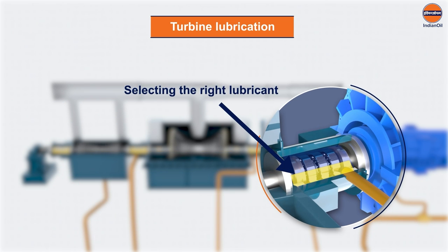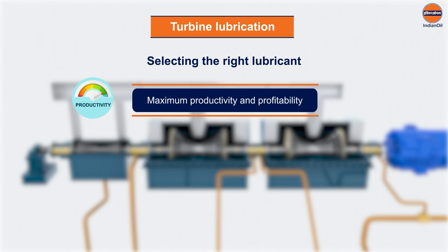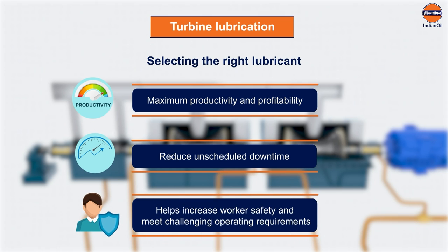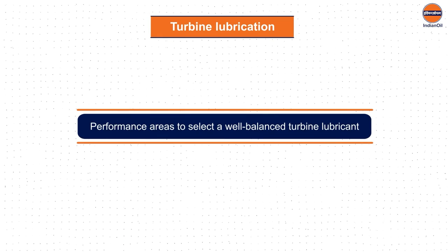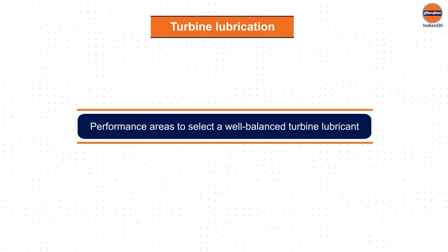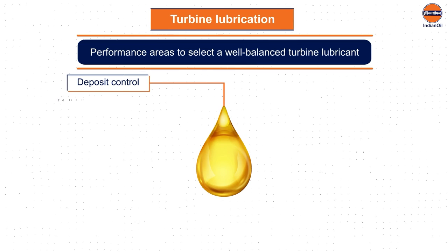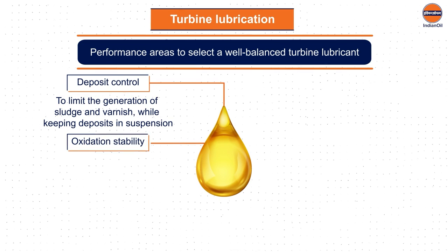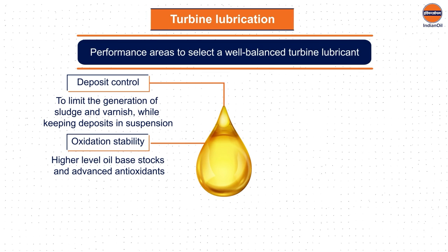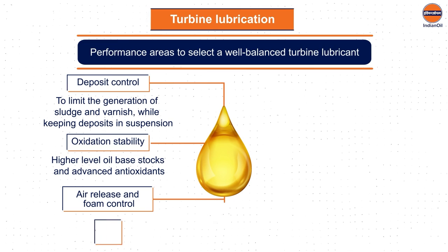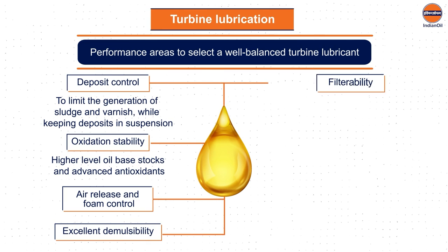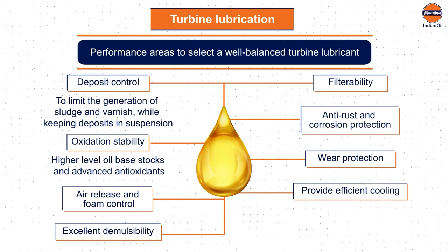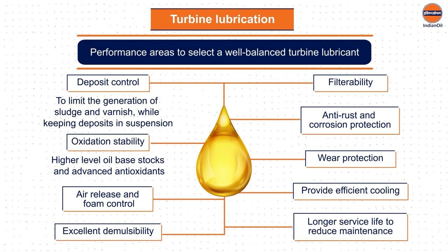By selecting the right lubricant, turbine operators can maximize production and profitability, reduce unscheduled downtime, increase worker safety, and meet challenging operating requirements. To select a well-balanced turbine lubricant, one should consider the following performance areas: deposit control to limit sludge and varnish, oxidation stability with higher-level oil-based stocks and advanced antioxidants, air release and foam control, excellent demulsibility, filterability, anti-rust and corrosion protection, wear protection, efficient cooling, and longer service life to reduce maintenance.